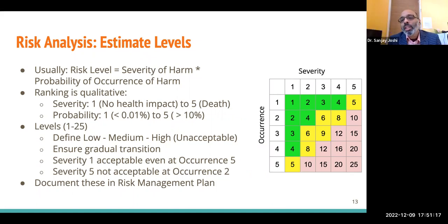Usually, if your risk management plan says that low and medium risks are acceptable, and after you did all your mitigations, each row of your risk analysis had either a green or a yellow, you're done, because none of your risks are unacceptable. I don't need a risk benefit analysis. You need to write that down in the report and get it reviewed and approved, of course.